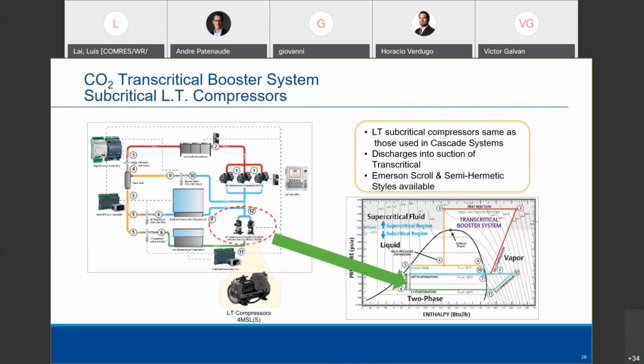It was basically taking the 410A scroll embodiment and making it CO2 ready, because the pressures of subcritical CO2 down here are pretty close to the pressures of 410A. And if you deal in 410A pressures on the air conditioning side, then you know that they can run up to 479 pounds at 130-degree condensing, which is about your discharge pressures of CO2 low temp.